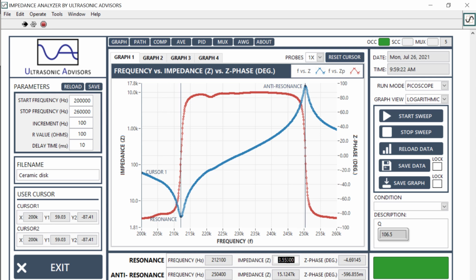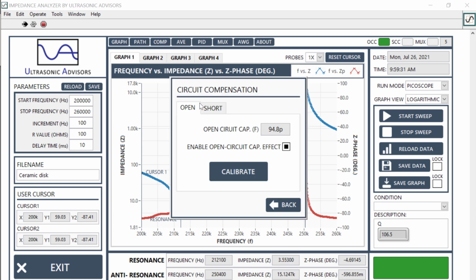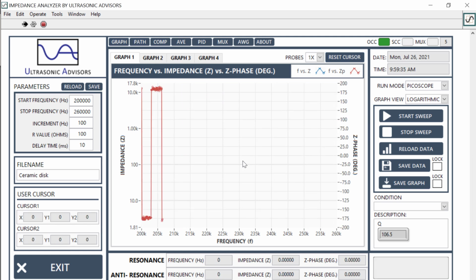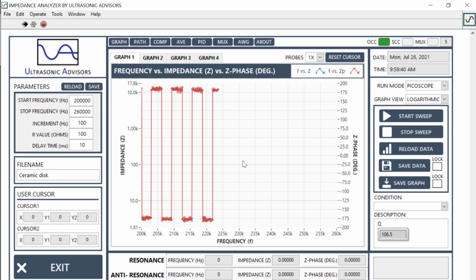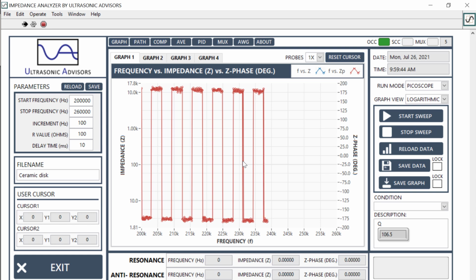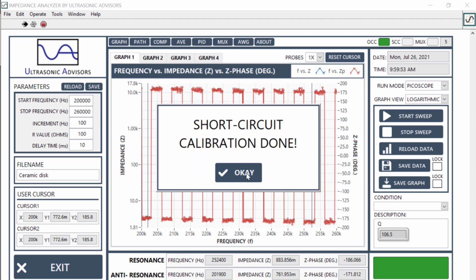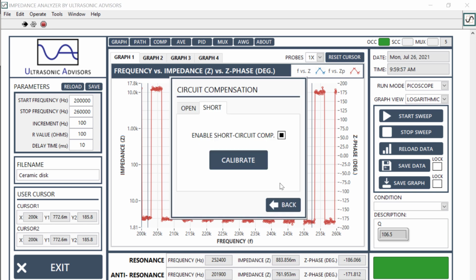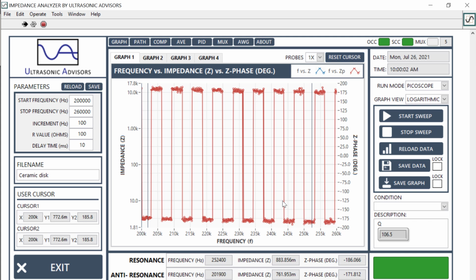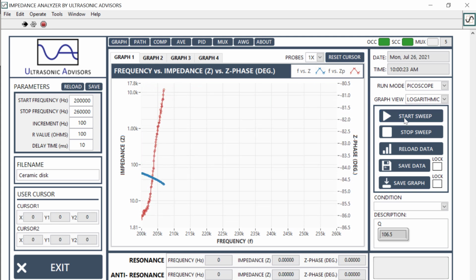In this case, I definitely would want to use short circuit calibration. So I'm going to do that because I haven't done it already. Compensate. Now I'll go ahead and reload it and test that again. When measuring impedance levels lower than 10 ohms, then short circuit calibration is going to be a good idea at that point, or if your cabling is not good. So I'll go ahead and redo that measurement.